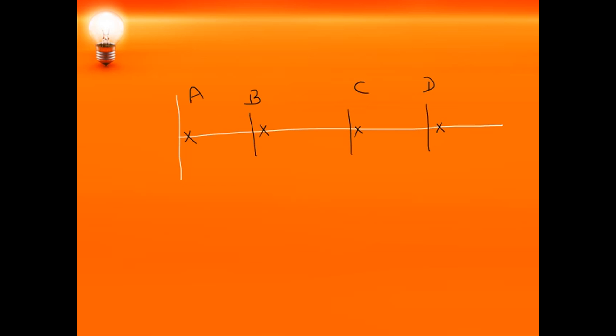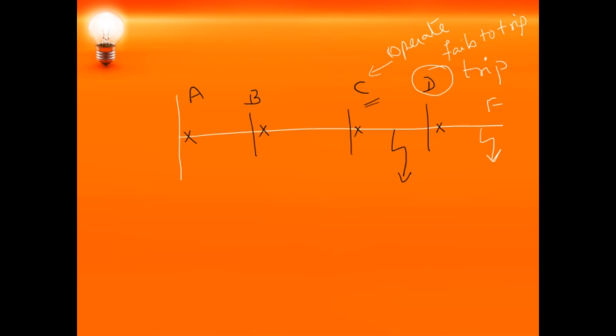Now how should the circuit breakers operate? Suppose a fault occurs beyond D — somewhere here — then the circuit breaker at D has to trip. The circuit breaker at D has to trip. In case the circuit breaker at D fails to trip, then the circuit breaker at C has to operate. That means circuit breaker C operates as a backup protective scheme. Likewise, if a fault occurs anywhere between C and D, then the circuit breaker at C will act as the primary circuit breaker.